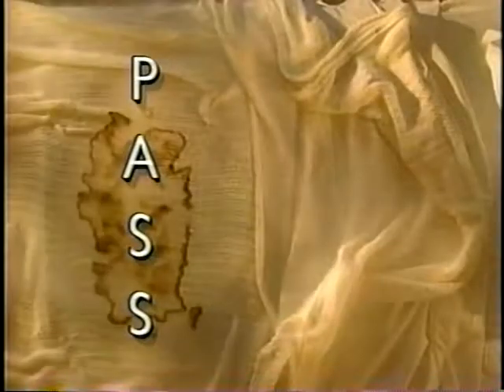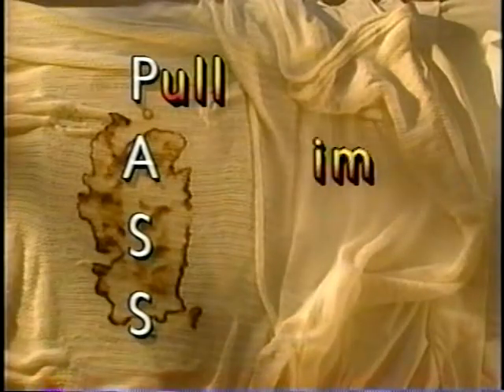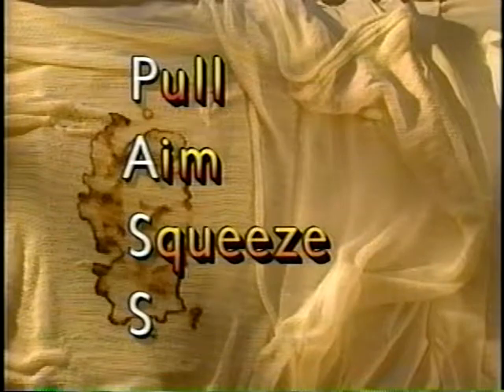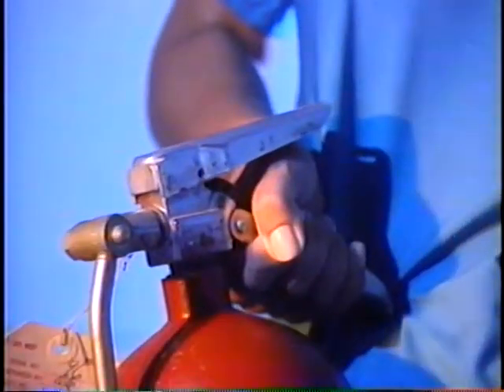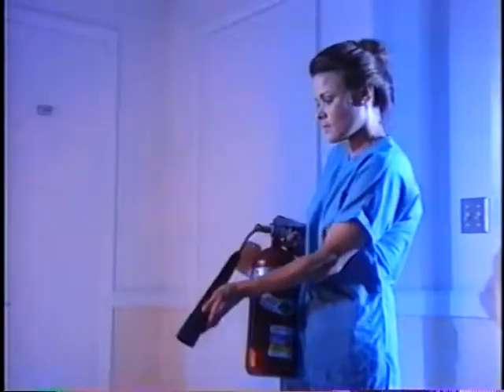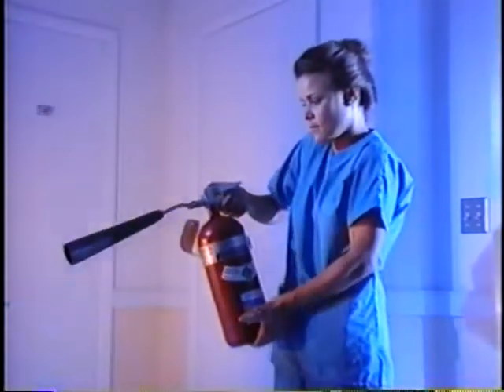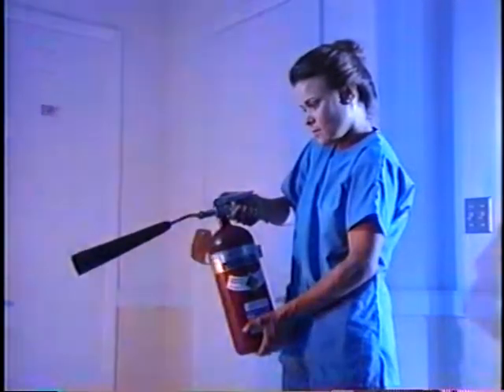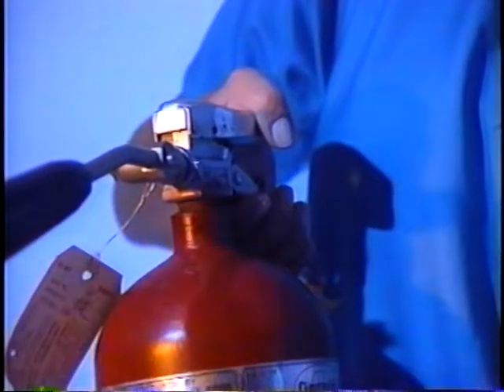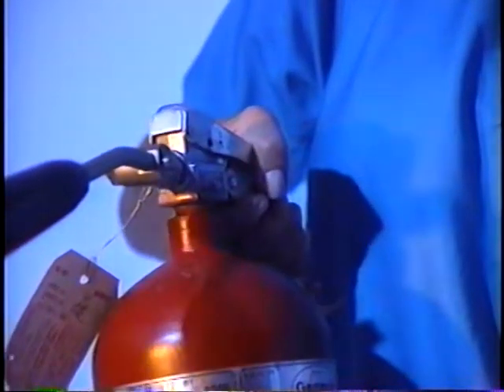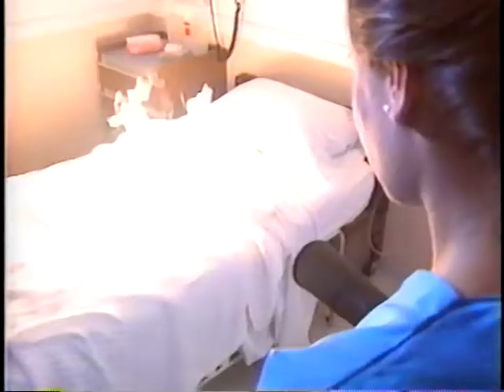Once you know the ABCs of fire extinguishers, your task is to pass the drill on using one. You simply pull, aim, squeeze, and sweep. Pull the pin between the 2 handles. Aim the nozzle at the base of the fire, since the pressure of spraying directly into the flames may spread the burning material. Squeeze the handles together.